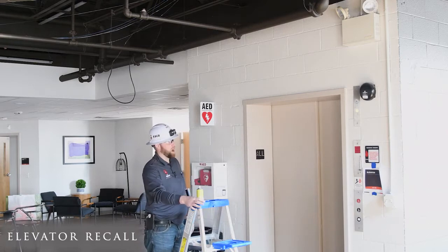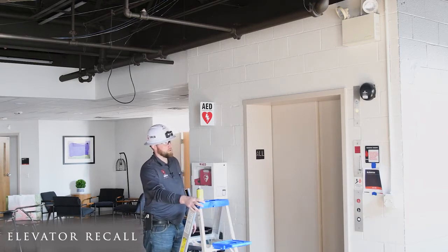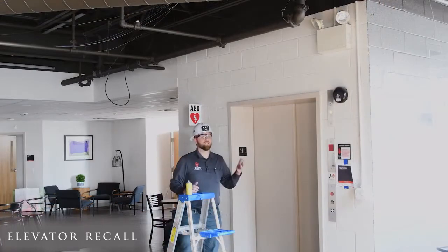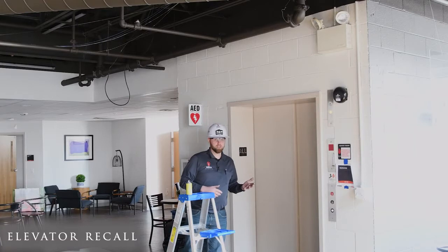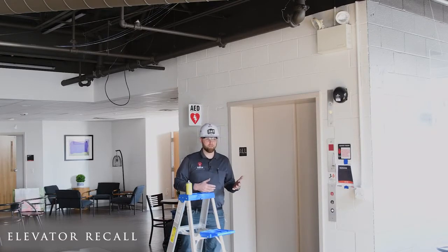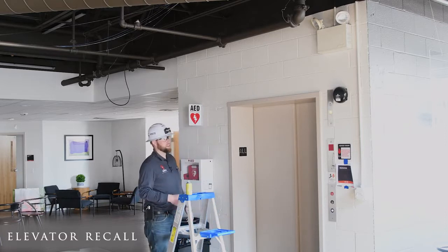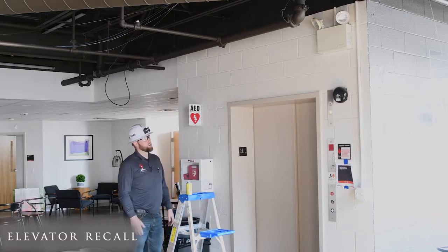My fire alarm just went into alarm. Right now the smoke detector is in verification mode. We have a 16-second verification programmed into it. So when it goes into alarm, it waits 16 seconds, and if it still sees a sampling of smoke in the chamber, then it goes into alarm. So there we've hit that 16 seconds and it's in alarm.